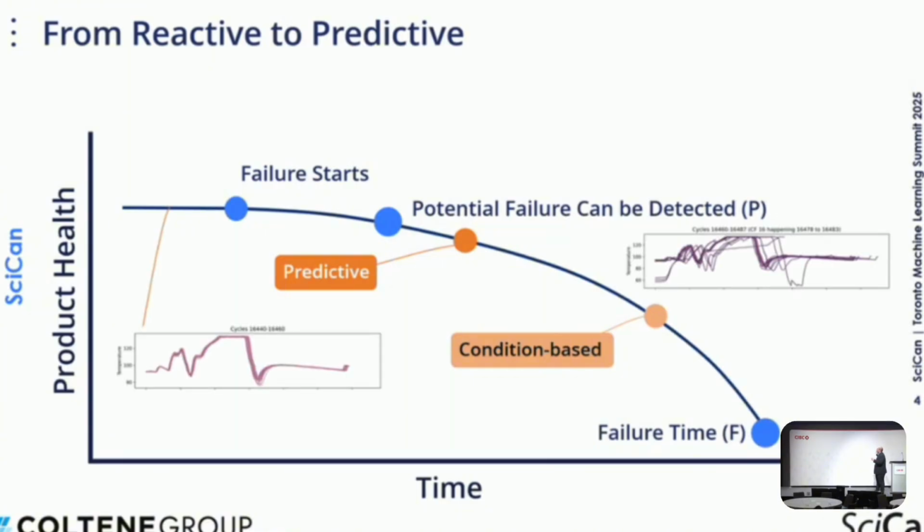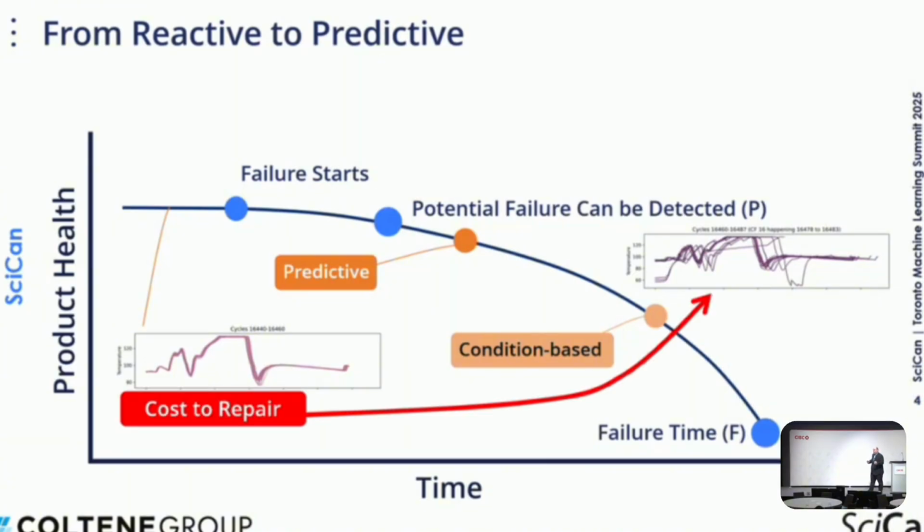I want you to look at one of the temperature versus time series that we have here. You have a pretty much good flow when the product has good health, and then you start to see these peaks and these valleys that could raise a red flag on the product health, and that could be used in advance so that we can predict and prevent the machine from going down completely. And that's very important because, like the TV, maybe it's just a dead pixel at the beginning, but then it could grow and damage other components, which then causes the whole cost of the repair to go up.